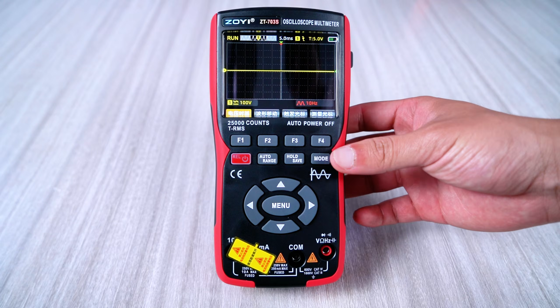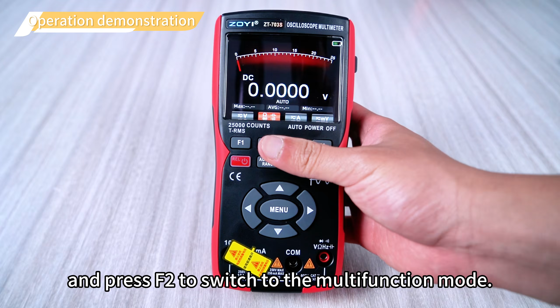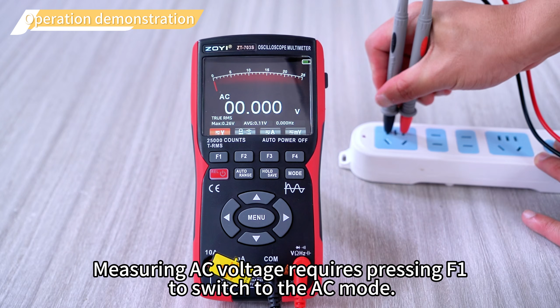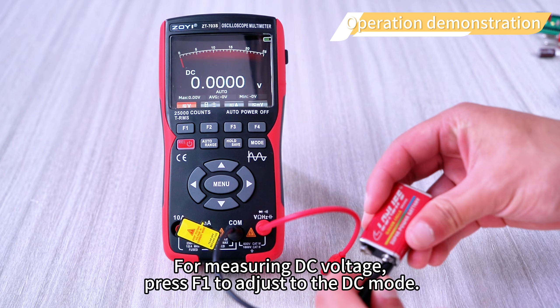To switch to the multimeter, press the mode key and press F2 to switch to the multifunction mode. Measuring AC voltage requires pressing F1 to switch to the AC mode. For measuring DC voltage, press F1 to adjust to the DC mode.